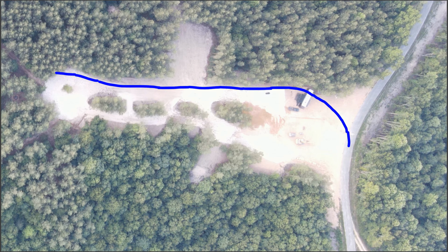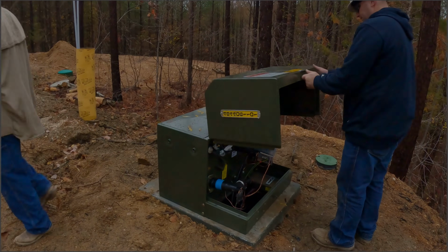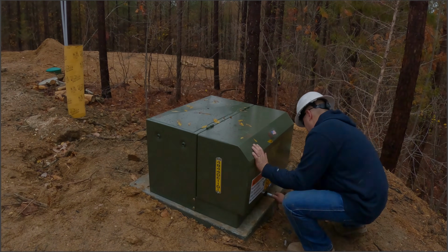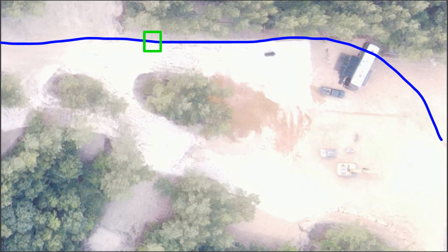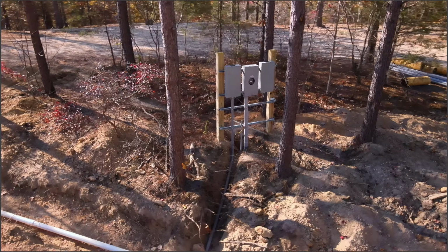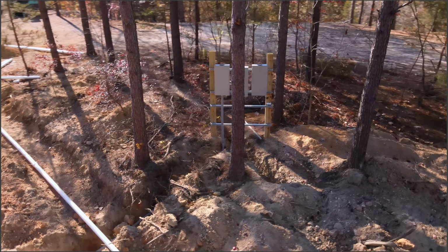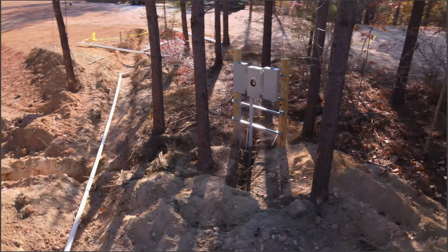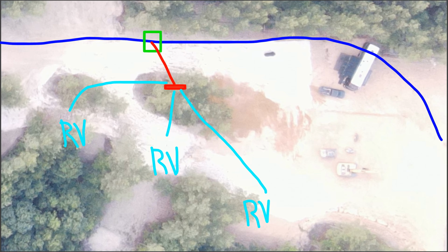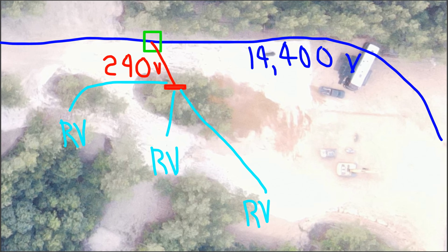We'll run that primary wire down the first 500 feet of Linden Camp toward the back. Once that 14,400 volt primary wire is in the ground, we can place transformers wherever needed. The first transformer goes here, across the driveway, feeding a power panel we'll be discussing in this episode, episode 2. From that power panel we'll connect RV and EV sites that need power. The transformer here steps that 14,400 volts down to 240 volts.